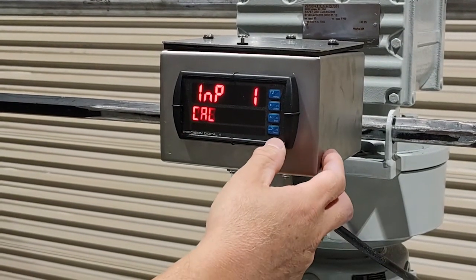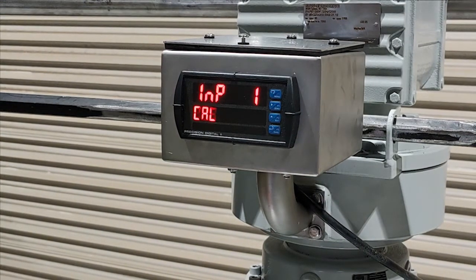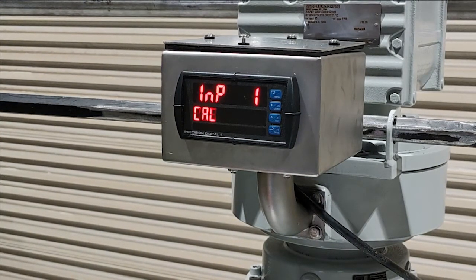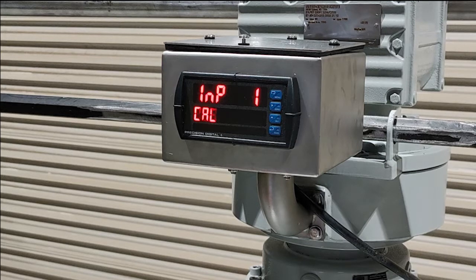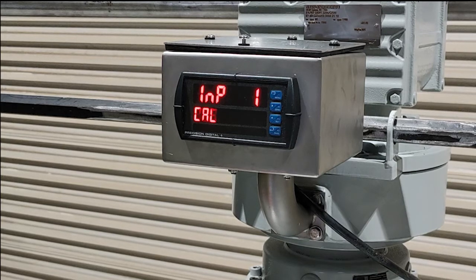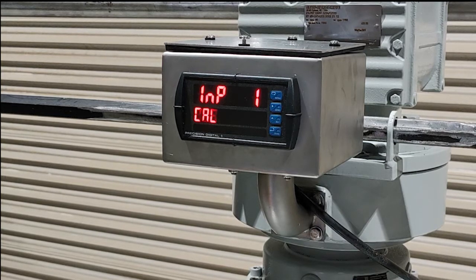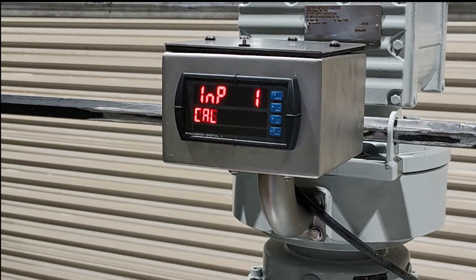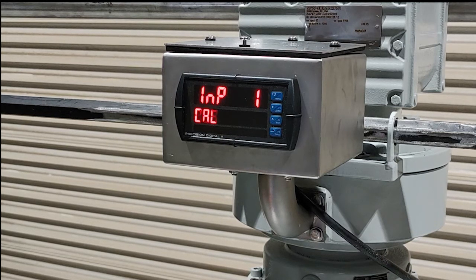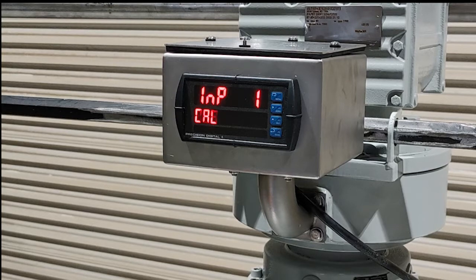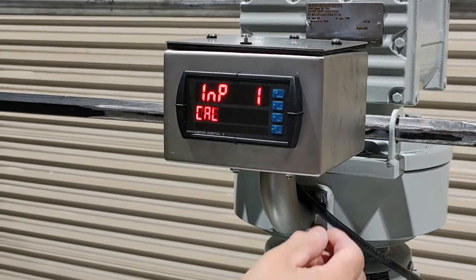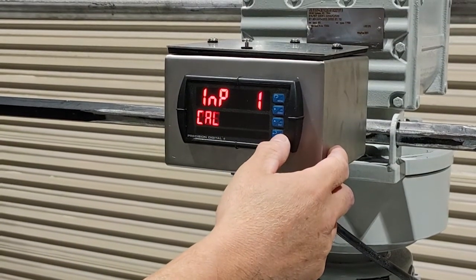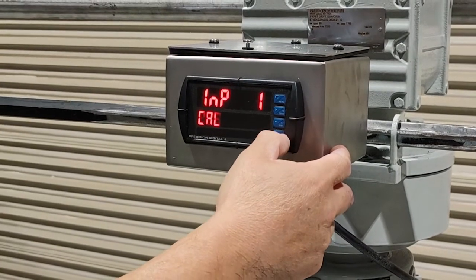The display on the screen should now read INP1. This means that the calibration program is looking for a rest state set point signal. Ensure that no torque or other outside forces are applied to the load cell, as any interference will skew the calibration. Press the Enter button to tell the program to collect the signal from the load cell.